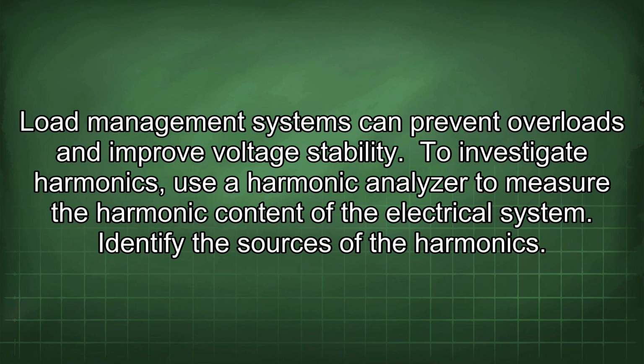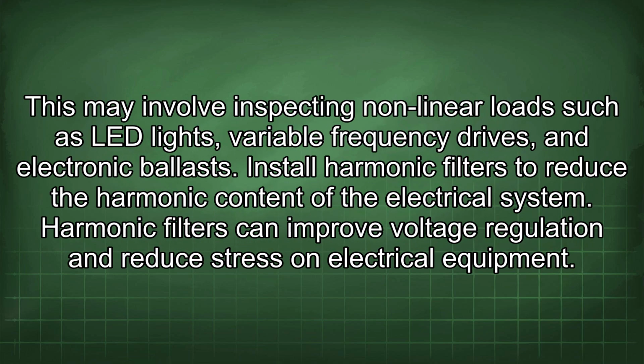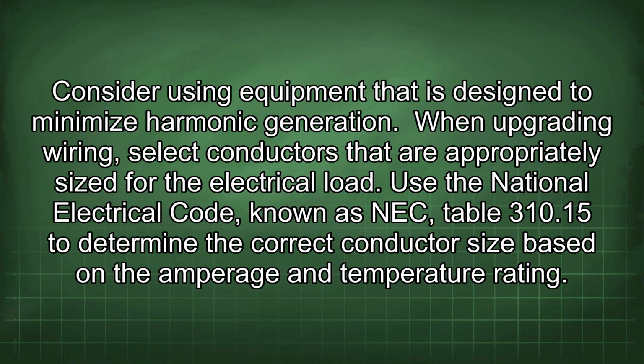To investigate harmonics, use a harmonic analyzer to measure the harmonic content of the electrical system. Identify the sources of the harmonics. This may involve inspecting nonlinear loads such as LED lights, variable frequency drives, and electronic ballasts. Install harmonic filters to reduce the harmonic content of the electrical system. Harmonic filters can improve voltage regulation and reduce stress on electrical equipment. Consider using equipment that is designed to minimize harmonic generation.